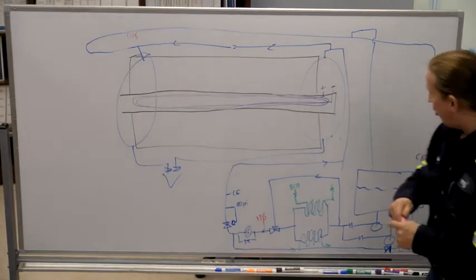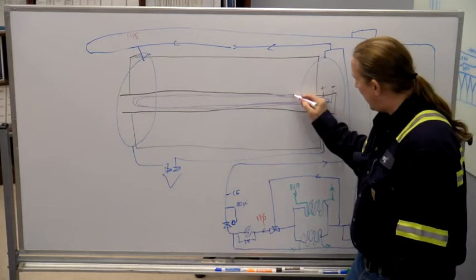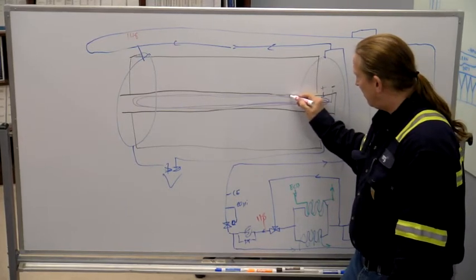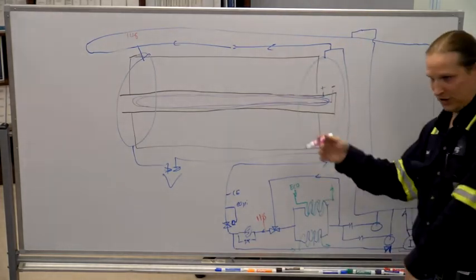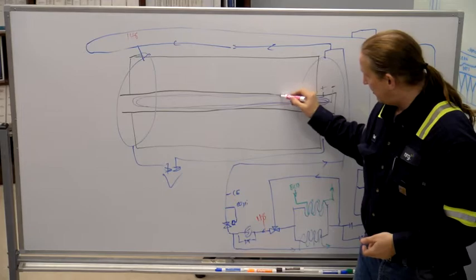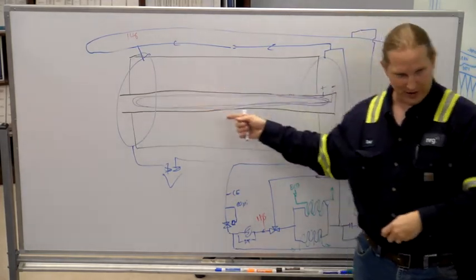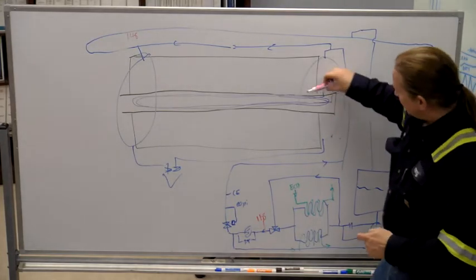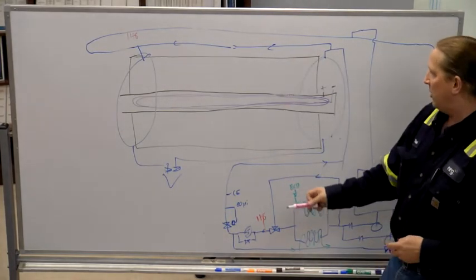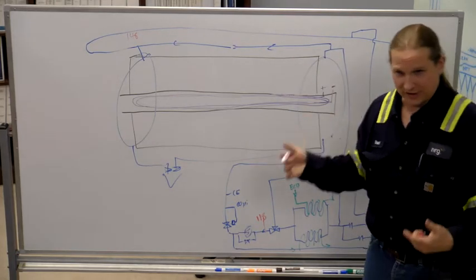Alright, so the rotor itself that's spinning 3600 rpms has little scoops built into the shell that grab the hydrogen and pull it down across the internal windings, and then spin it back out. And so these scoops kind of alternate as you go down the rotor. As the hydrogen absorbs the heat off the rotor, then the side that's rejecting it spits it out, and we have to get rid of the heat somewhere.